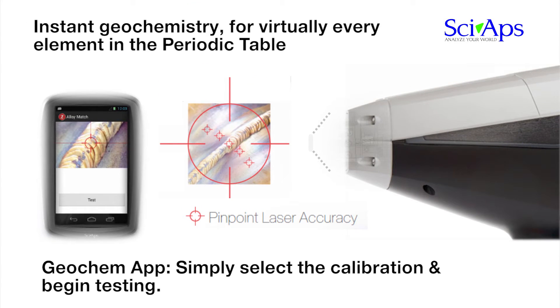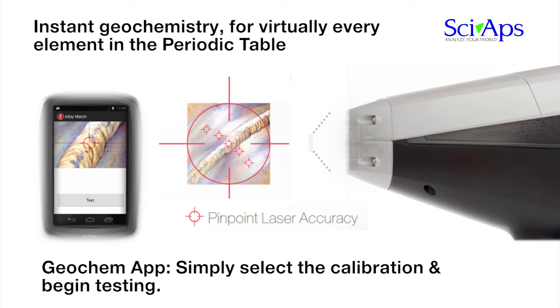For the Geochem app, users can create, store, and utilize specific calibration methods created for a multitude of ore bodies and soils. The SciAps Z also addresses two different applications in Geochem: the 2D rastered beam allows for a good average concentration of Geochem samples to be determined. However, if you want to zero in on a mineral vein or inclusion, the laser and camera combination allows precise targeting.